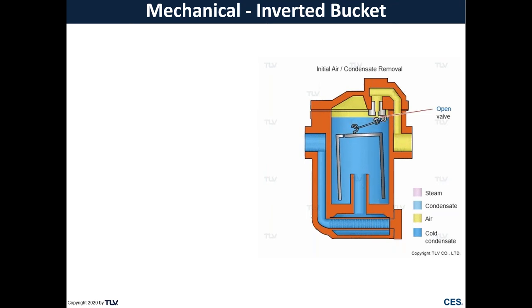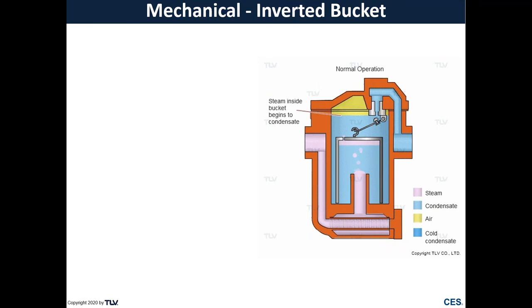Now, when there's air in that bucket, there's actually a tiny weep hole that slowly bleeds that air, and that's how that trap gets rid of the air in the system, just during startup. So as we get closer to our steam interface, you'll begin to get steam introducing to this trap, filling up that bucket, giving that bucket buoyancy again, which then closes off the trap.